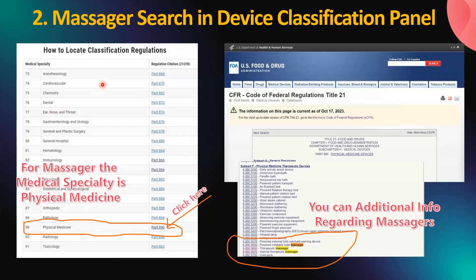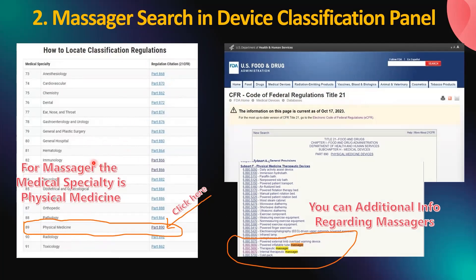The device classification panel is different from the product classification. According to the U.S. FDA, most medical devices can be classified by finding the matching description in Title 21 of the Code of Federal Regulations (CFR), parts 862 to 892. The FDA has classified and described over 1,700 distinct types of devices, organized into 16 medical specialty panels such as cardiovascular devices or ear, nose, and throat devices. Using the example of a massager, the medical specialty is physical medicine. Clicking on this will take you to the physical medicine section where you can find different types of massagers classified based on the Code of Federal Regulation 21.